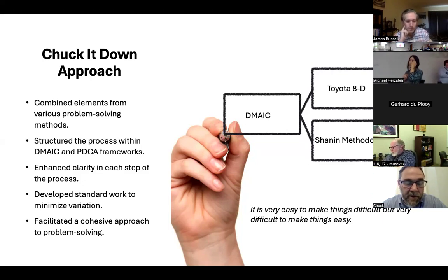So I knew the problem was there, and we started following the process, trying to break down the point of occurrence. I grabbed one of the engineers and some operators, and we did a high level map of the process, kind of what I told you. We buy it in big chunks, we bring it in, we receive it, we send it through a clean room that breaks it into smaller chunks. We then package that and send it to the line. The line sends it through the machines. It makes the catheters, it's inspected, and then it's packaged.